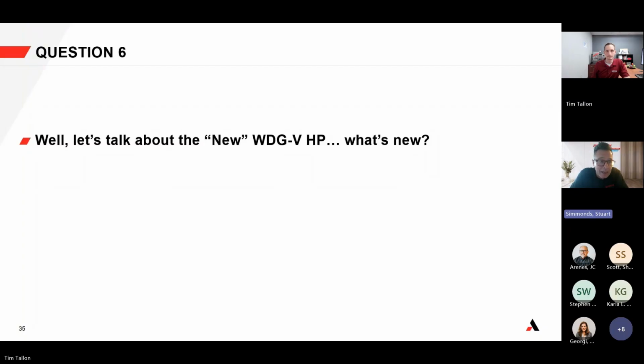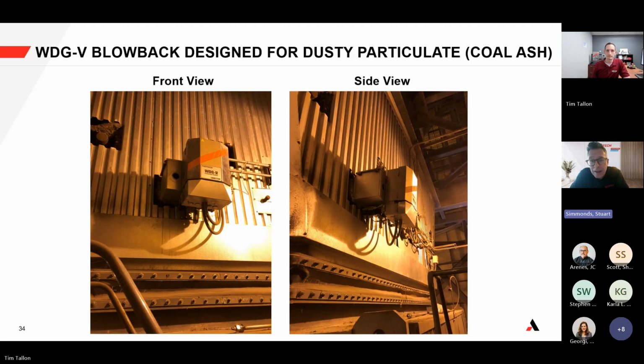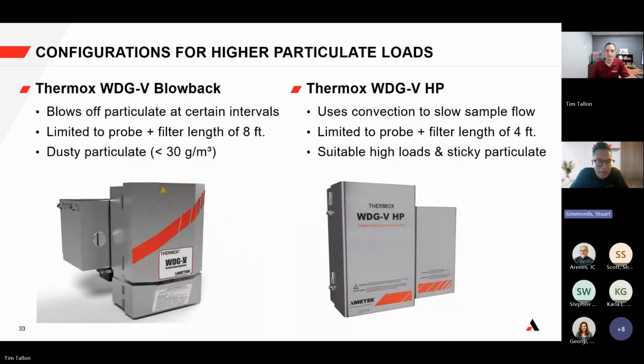And in your picture there, inside is great. So we've got blowback, it's inside, we don't have to worry about the cool air coming in. But one of our problems with blowback, as we found out in Canada, is the moment we've used that chamber up on the inside, we're sucking cold air from the instrument air. And when cold air in winter is extremely cold, we end up with dew point concerns. So we're somewhat nervous about it, unless it's an indoor application, as you say.